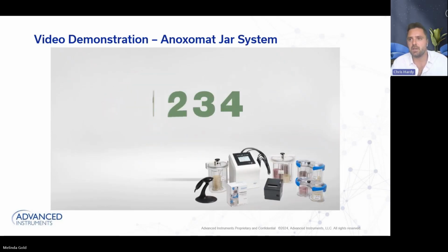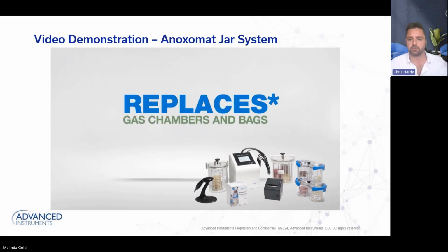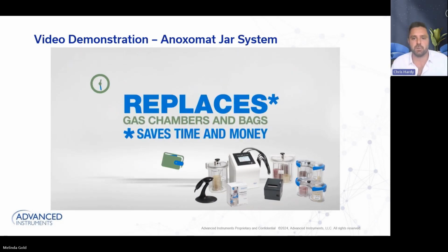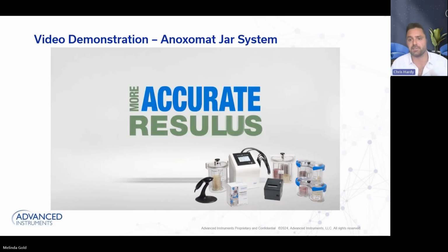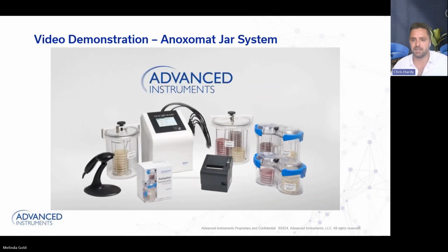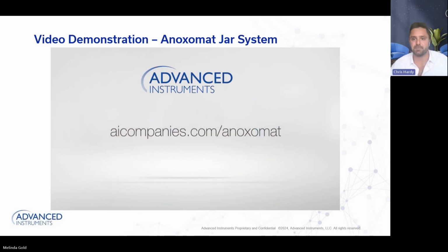But this is pretty much with all those tests, and I need to highlight those tests because that's the biggest proponent of this system. It's rather than you putting a plate inside a bag with a sachet, thrown in the incubator, and maybe 24 hours later, your indicator strip didn't turn colorless, and now you got to do things over again. Or maybe your chamber needed maintenance and it broke down overnight on third shift, and you only had one person on shift to try to fix it, and you got to redo all those samples too.